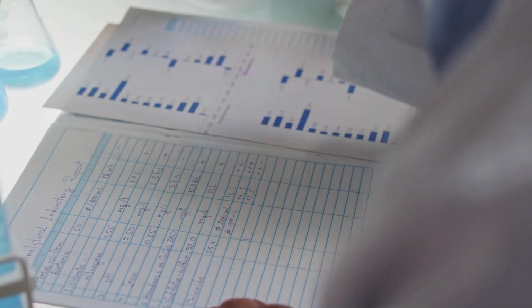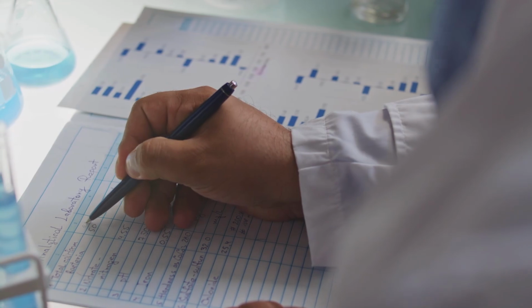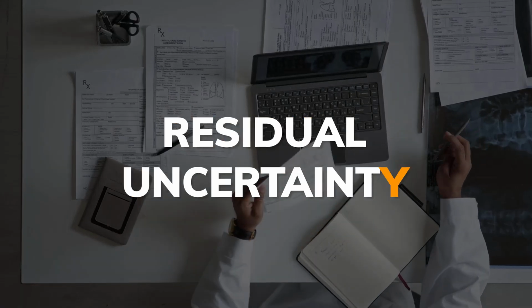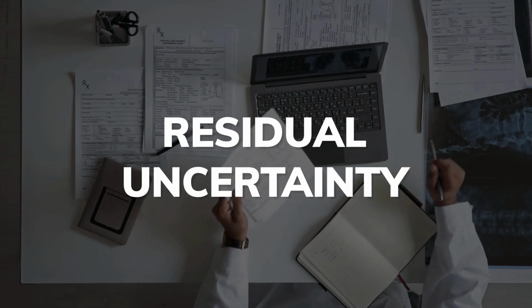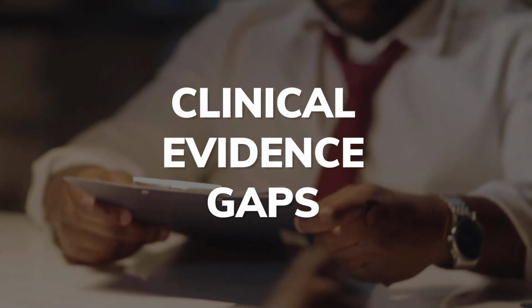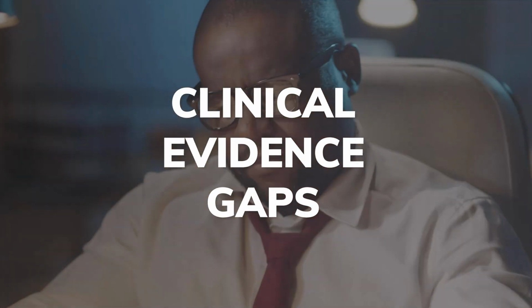So post-market clinical follow-up surveys can be used to address residual uncertainty from your risk management file or clinical data gaps identified in your clinical evaluation, but they only work as intended if they're set up properly from the start.